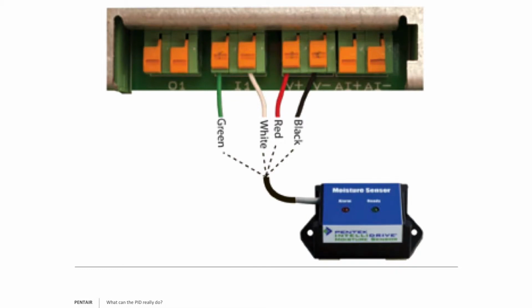So in this case here, the water sensor, when the probe set that's on the bottom of this unit has water touching it, it makes the connection and applies voltage to input 1. We would then set input 1 to external fault. Because if I have a pipe break and I'm sensing water leaking everywhere, the source of that water potentially leaking everywhere, of course, is going to come from the pump running. So I want to stop the pump. So in this case, we definitely do want a hard stop. So this is just one example of one device that can be hooked up to this unit.